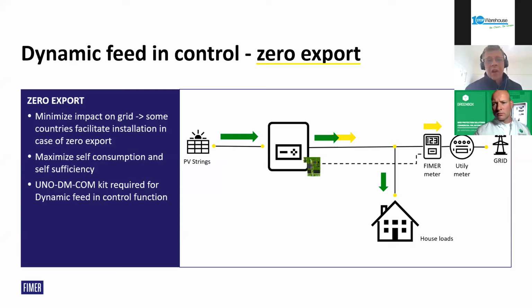So it does have the functionality of the dynamic feed in control. If you have any requirements from the DNSP for zero export, export limitation, or if the focus of the installation is for self-consumption, you would need the COM kit, as you can see in the little drawing here. You connect that inside the inverter, RS485 to the energy meter, and you have all the functionality for dynamic feed in control.